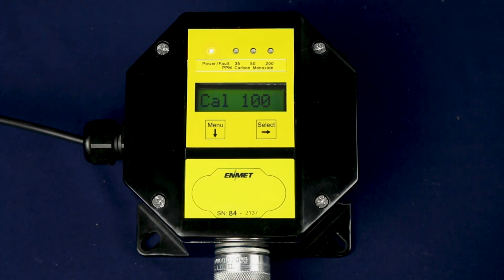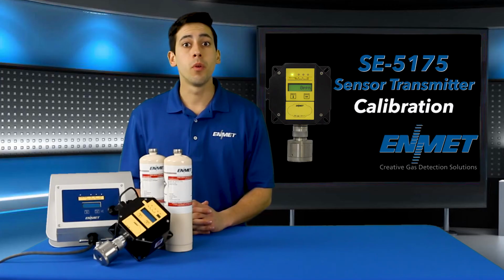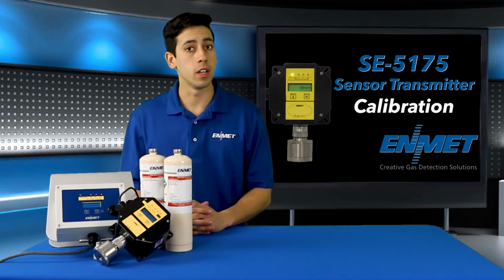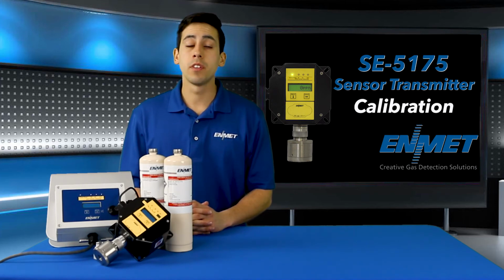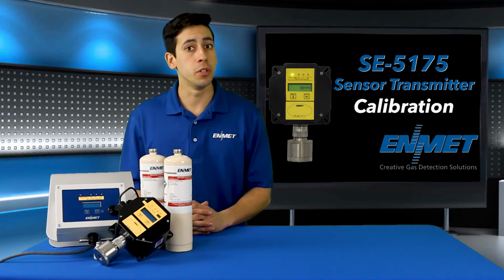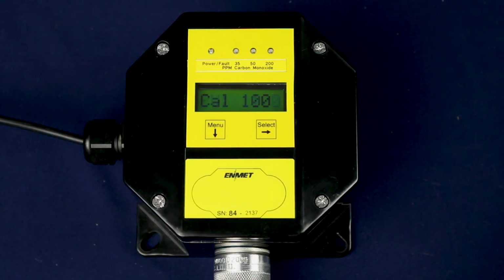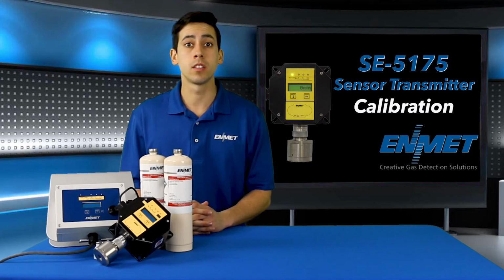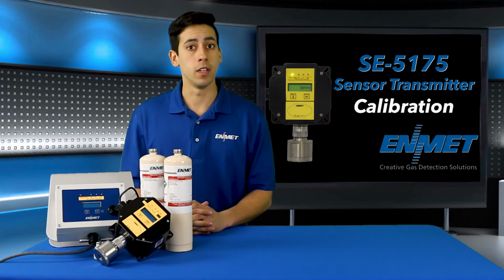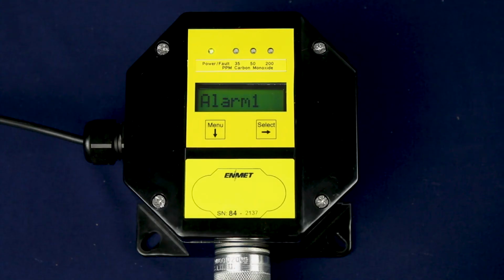The display will alternate between the span concentration, in this case it is Cal 100, and PV. PV again stands for present value. The transmitter will monitor the sensor signal for stability for 2 minutes. If the sensor signal is stable after 2 minutes, the new span point will be accepted and Cal OK will be displayed, indicating a successful calibration. You will be returned to the maintenance menu with the Alarm 1 option highlighted.